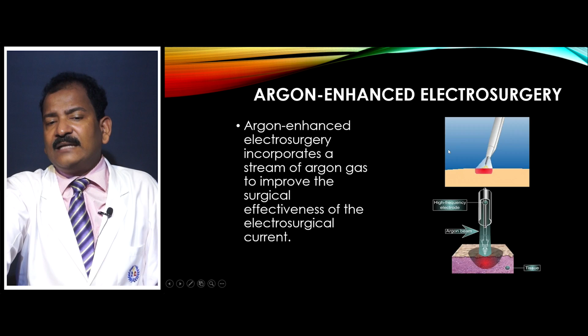So, what to do? Argon gas was used. This is the same monopolar electrosurgical generator, and there is an argon tube here through which the argon beam is discharged. Argon is a peculiar gas, an inert, non-combustible, easily ionized gas, and it creates a bridge between the electrode and tissue. It is heavier than air, so it displaces nitrogen and oxygen also. So, what will it do? It will improve your ability to fulgurate.